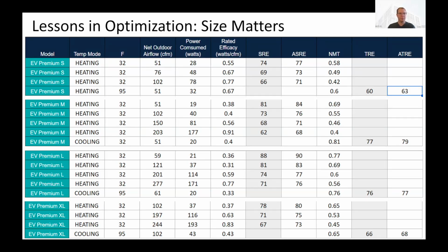And we can compare some of these between the two. Let's just take the Premium M at 51 CFM, and compare that to the Premium S at 51 CFM. That's the first row on each of those entries. And we see that at that same 51 CFM, the power is higher in the smaller unit. Again, it's trying to move more air through a smaller heat exchanger core, and therefore the sensible recovery efficiency is 77 rather than the 84 apparent sensible recovery efficiency for the Premium M.